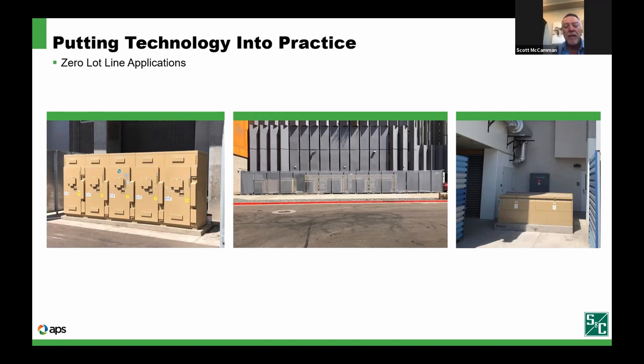On the far left is an example where the lot line is literally right at the edge of that concrete, and there's an alley adjacent to this building, so it gives plenty of room for access to this equipment. The middle picture is basically a public street, and you can see the public sidewalk there as well. These cities are also looking to screen in the equipment, so that's also been a challenge to meet our clearances for safety and for the crews. But we are working together with the cities, and it's working out quite well.